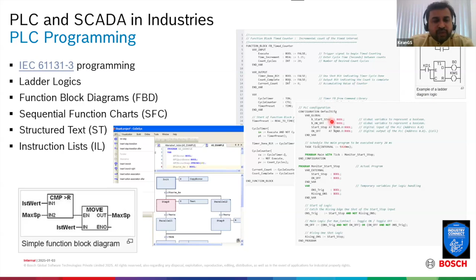But when you try to map this to the scan cycle, you need to be careful that your physical output, like the QX0 on-off, would be set only after it has fully completed reading the input, executing the program, and then finally setting the output. Till then, there is a possibility that a particular signal may not be updated unless it has come to the next scan cycle. That perspective you'll have to take care of in any PLC program.